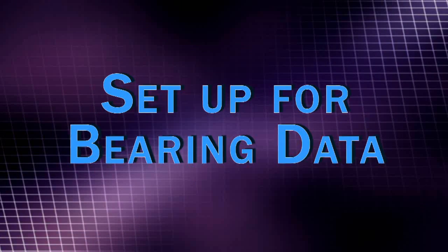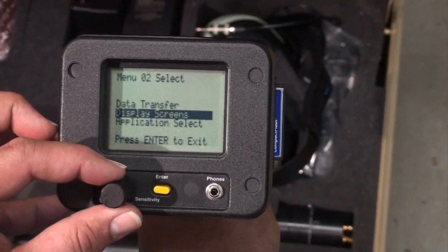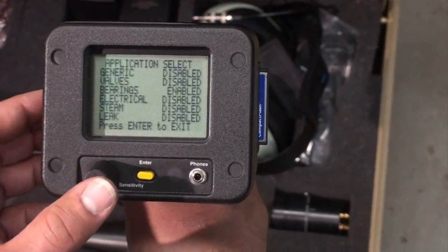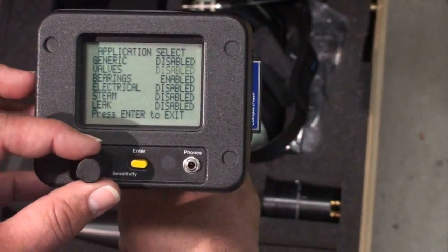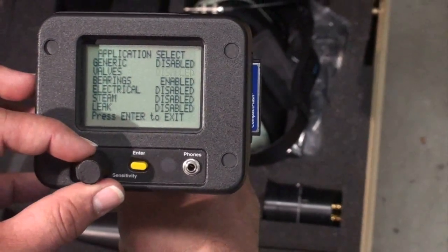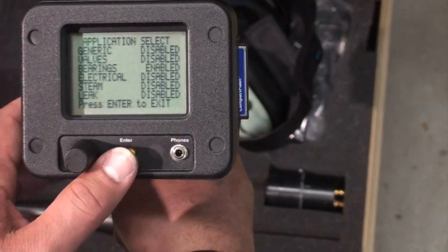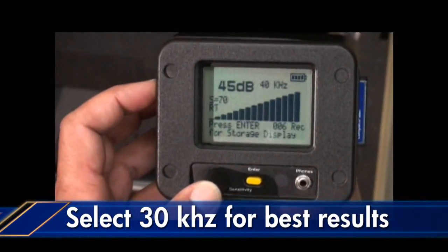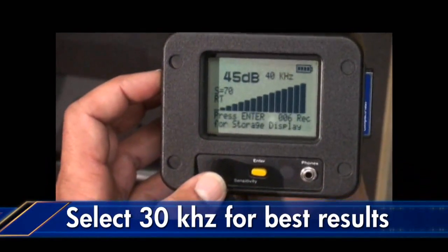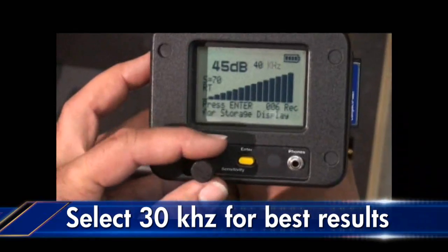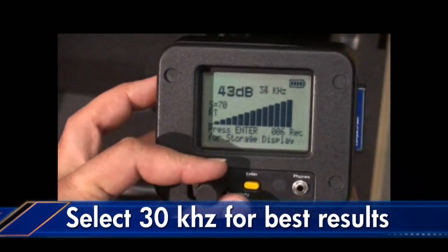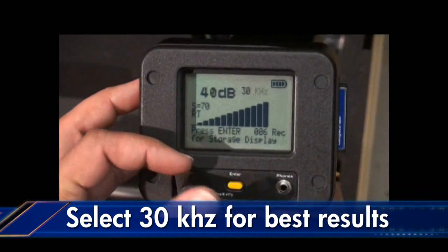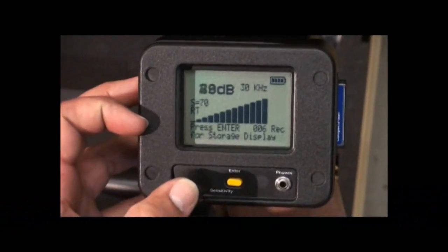Now let's set up for testing and collecting bearing data. First, open the application select menu and select the bearing application. Next, we'll use 30 kilohertz for best results when testing mechanical equipment. Here we're spinning down to 30 kilohertz and selecting it, as demonstrated.